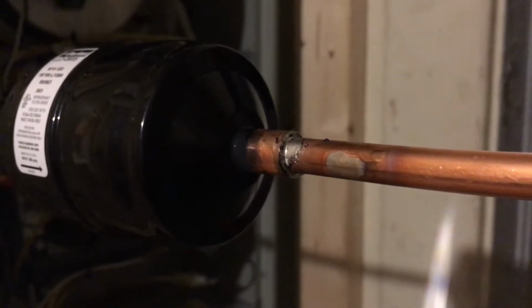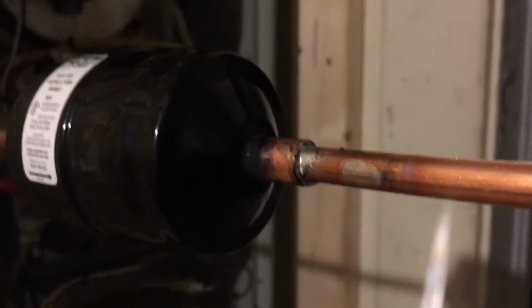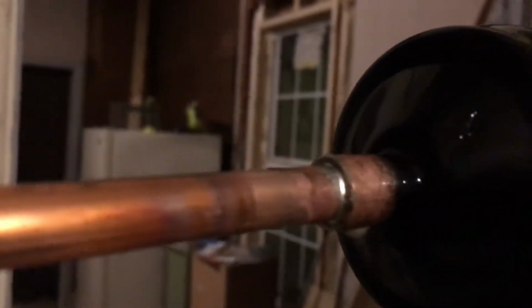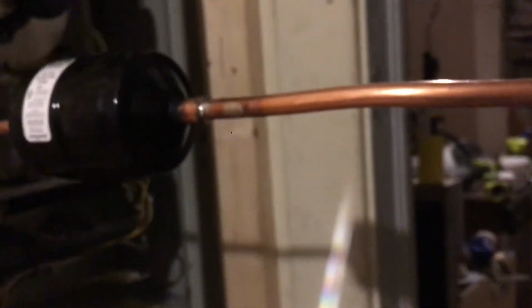Okay, I decided to go ahead and start soldering up these lines. I just did the liquid line filter dryer. There's my soldering job, Stay Bright 8, soldered with the yellow MAP gas torch. As you can see, I'm a firm believer the liquid line filter dryer belongs indoors, out of the weather, because it's made of painted steel. If you put it outside, the paint can deteriorate and it'll rust and you get a leak. But if you put it indoors, you don't have to worry about it. Let me finish soldering this up.